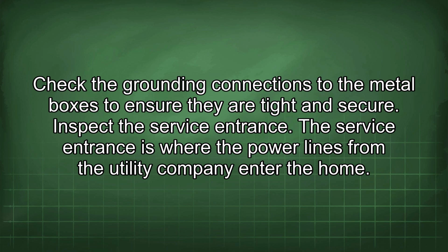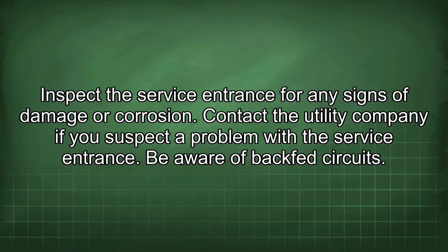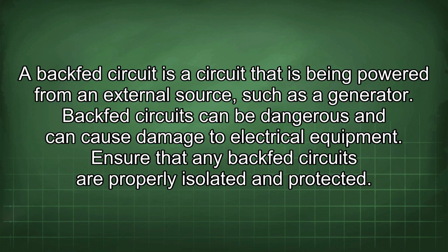Inspect the service entrance. The service entrance is where the power lines from the utility company enter the home. Inspect the service entrance for any signs of damage or corrosion. Contact the utility company if you suspect a problem with the service entrance. Be aware of backfed circuits. A backfed circuit is a circuit that is being powered from an external source, such as a generator. Back circuits can be dangerous and can cause damage to electrical equipment. Ensure that any backfed circuits are properly isolated and protected.